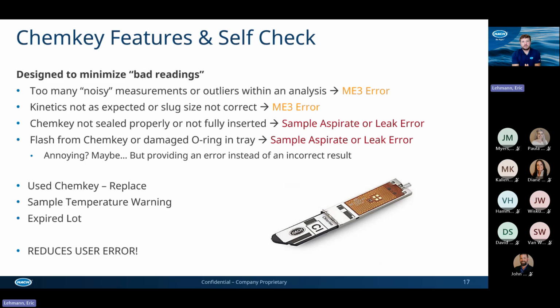It comes equipped with a checks and balances system. When the Chemkey is placed into the instrument, it's going to scan it and detect a number of different errors. For example, maybe there are too many noisy air measurements, maybe the turbidity was too high, maybe too many bubbles. Maybe you had a slug of sample or particulate coming through. It's going to give you an error. Maybe the Chemkey is not seated properly, or maybe it's damaged. It's going to give you an error warning or error message. Could this be annoying? Maybe, but it's also providing you with an error rather than an incorrect result. I'd much rather have the instrument tell me, hey, something is wrong with this measurement, rather than, as in traditional methods, getting a reading that is inaccurate or incorrect.